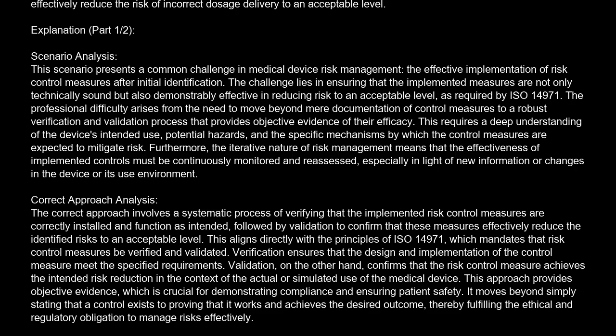Correct approach analysis. The correct approach involves a systematic process of verifying that the implemented risk control measures are correctly installed and function as intended, followed by validation to confirm that these measures effectively reduce the identified risks to an acceptable level. This aligns directly with the principles of ISO 14971, which mandates that risk control measures be verified and validated. Verification ensures that the design and implementation of the control measure meet the specified requirements. Validation, on the other hand, confirms that the risk control measure achieves the intended risk reduction in the context of the actual or simulated use of the medical device.